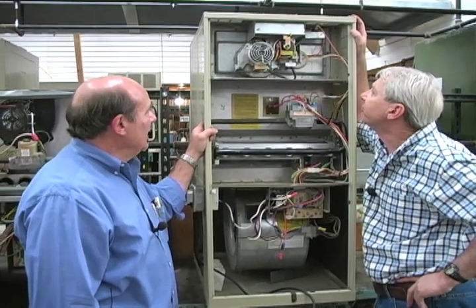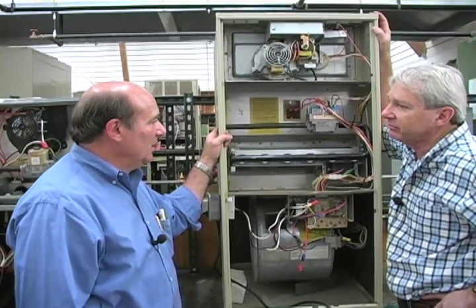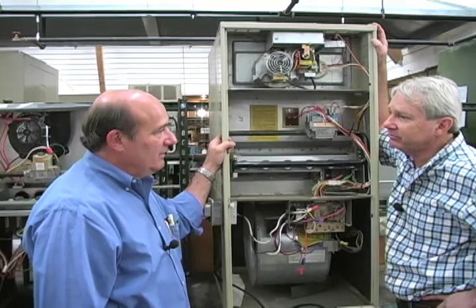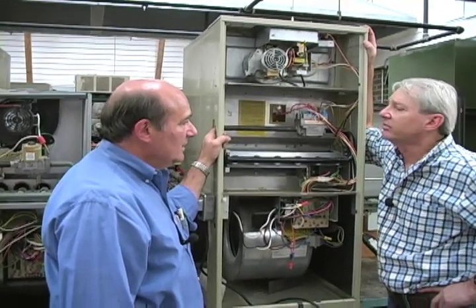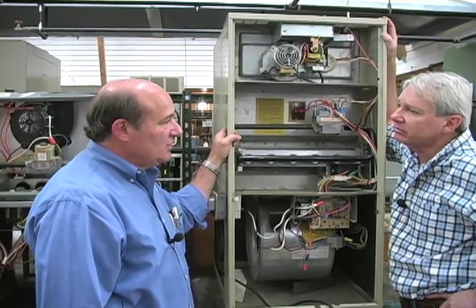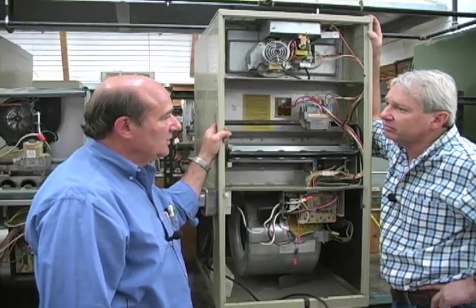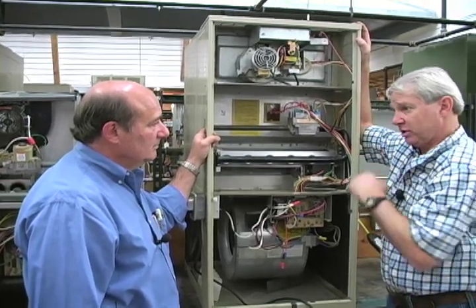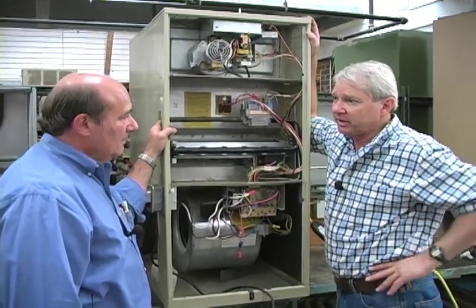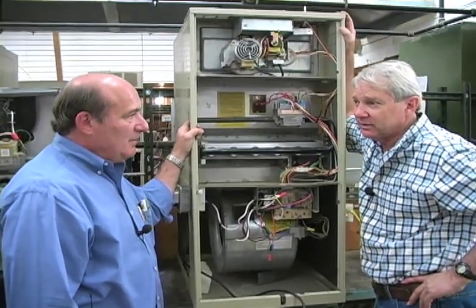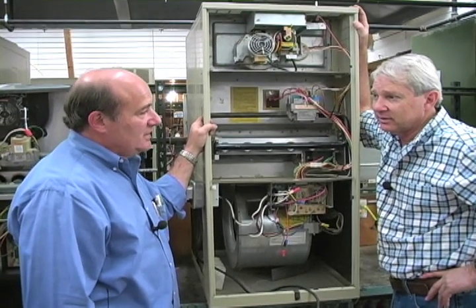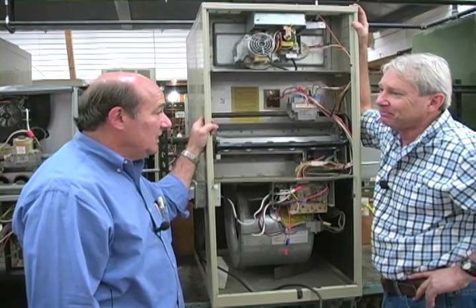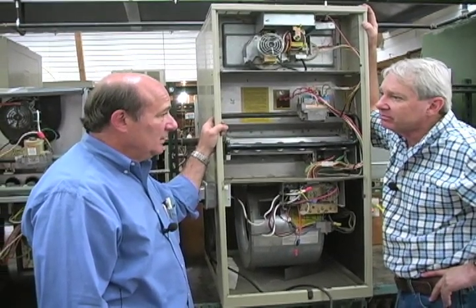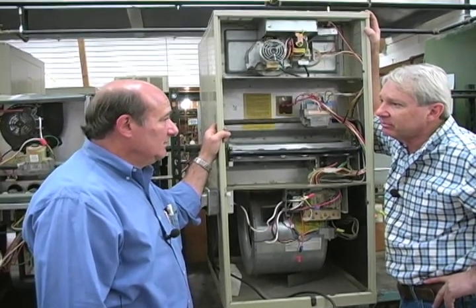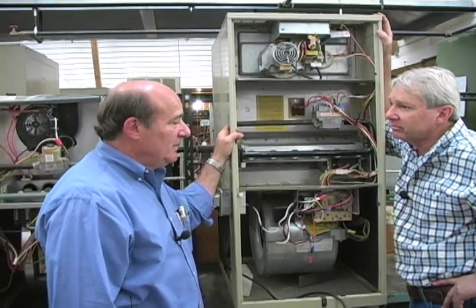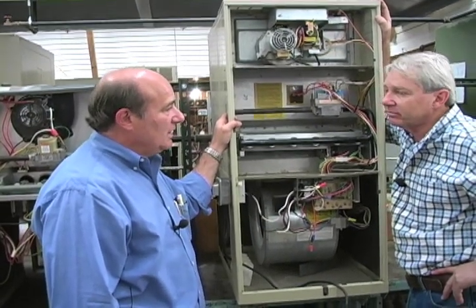So, they don't make an infinite number of sizes. They don't have a combustion blower for a 40,000 and a 60,000 and a 75 and a 100. They probably have one or two sizes, and so the manufacturer of the equipment will restrict that flue based upon how big his burner is in his furnace. Right. So unless you see discoloration or especially corrosion, not necessary to recommend call it a defect or recommend servicing. Well, it's probably not a design defect, but it may indicate that furnace has seen an awful lot of life. And if, for instance, that restrictor that's in that exhaust port were to burn out completely, then you could very easily develop an overpressurization of that flue and be driving carbon monoxide back down into the house from the water heater when the furnace is running.